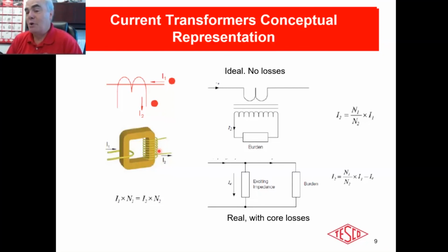The best reason to go to unity is that it makes the guys in the billing department often get their math wrong. You tell them it's an 800 to 5 and they say, oh, so what's my ratio there? Is that a multiplier of 100? No, it's 800 to 5. Just divide 800 by 5. That's 160 as your multiplier. Oh, okay. There are a lot of billing errors that have come up over the years strictly as a result of somebody doing that division incorrectly, getting the wrong multiplier after dividing 400 by 5 or 800 by 5 or 1,000 by 5. You'd be surprised, or maybe you wouldn't.